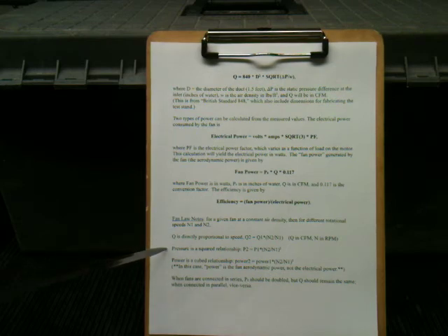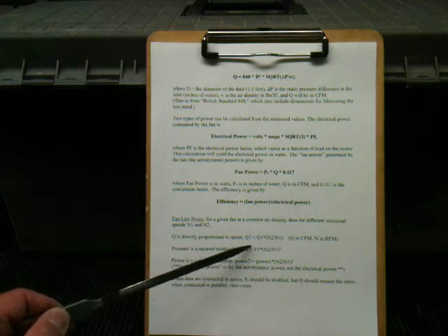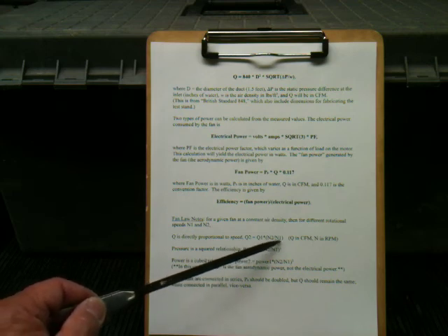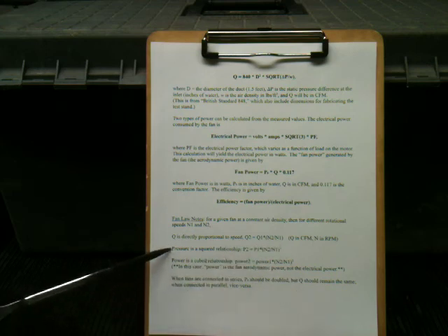Same thing with the pressure, that is a squared relationship. So P2 equals P1 times the quantity N2 over N1 squared. So see if that holds, again, for the two single fan configurations, 10 horsepower and single 5 horsepower. And then look at the fan power as a cubic relationship.